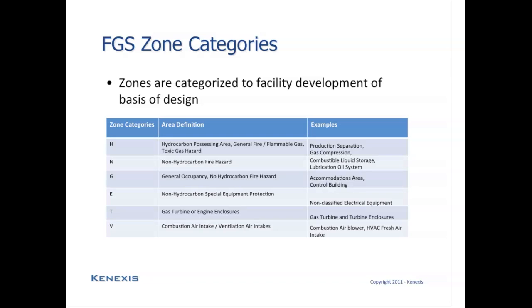The next type of zone is type N. Now, these are still process areas, and these process areas still contain fire hazards, but they may be non-hydrocarbon fire hazards. And this could include things like combustible liquid storage, such as methanol storage tanks, or possibly lubricating oil systems. The reason that these zones need to be separated from the traditional hydrocarbon processing areas is that the sensors that are used to detect these fires may be different from those that would be used in the traditional processing areas. And also, the countermeasures that are used in these zones may be different from the traditional process areas.